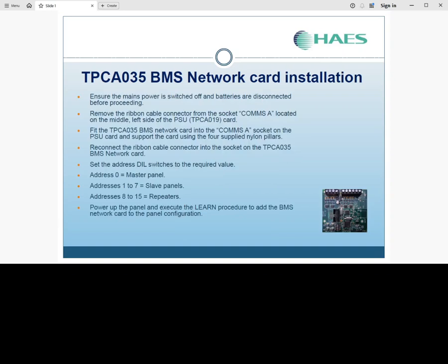The BMS network card installation. Ensure the mains power is switched off and the batteries are disconnected before proceeding. Remove the ribbon cable connector from the socket marked COMMS A located on the middle left-hand side of the PSU card. Fit the TPCA035 BMS network card into the COMMS A socket on the PSU card and support the card using the 4 supplied nylon pillars. Reconnect the ribbon cable into the socket on the TPCA035 BMS network card.